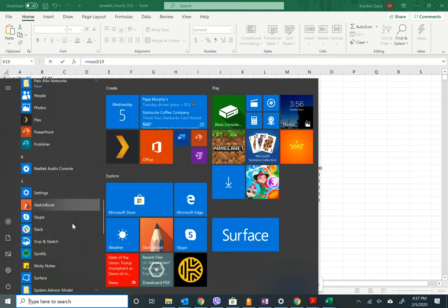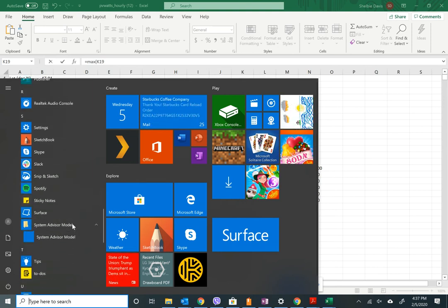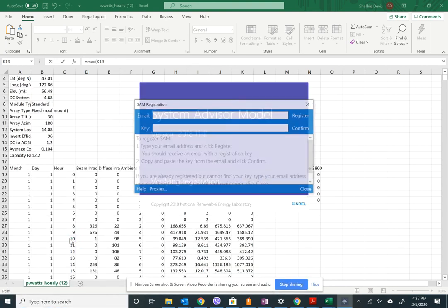Can I ask you a quick question? Yeah, absolutely. What would we do if the clipping was, how would we know when the clipping is too much? I would say that if you are getting clipping probably multiple times a week, that'd be too much. If you get it once a month for one period of time, that's probably not a big deal. I don't have a good rule of thumb for it because most of the time, after you do all the other sizing, you probably are fine. It's just an extra measure to make sure.